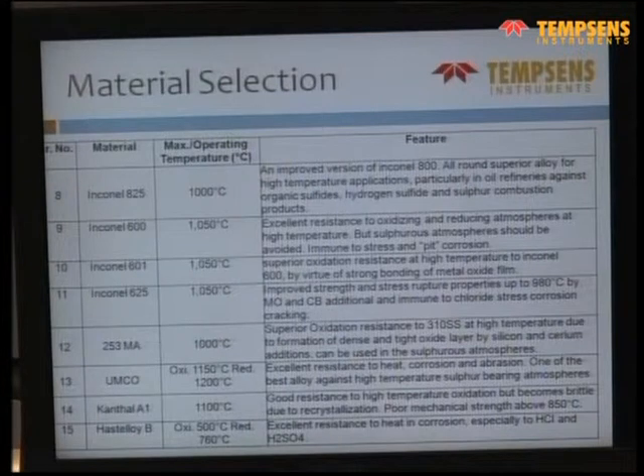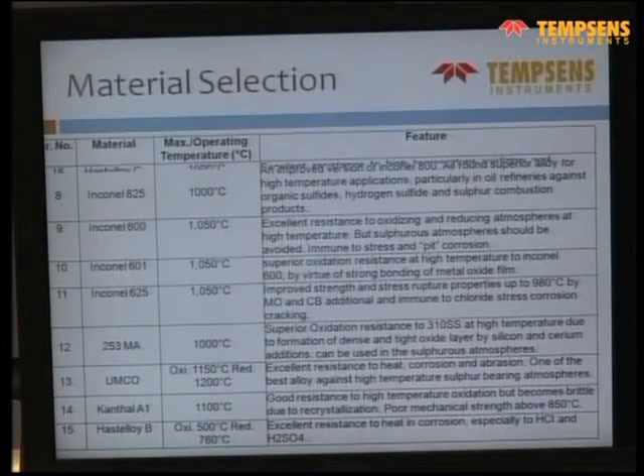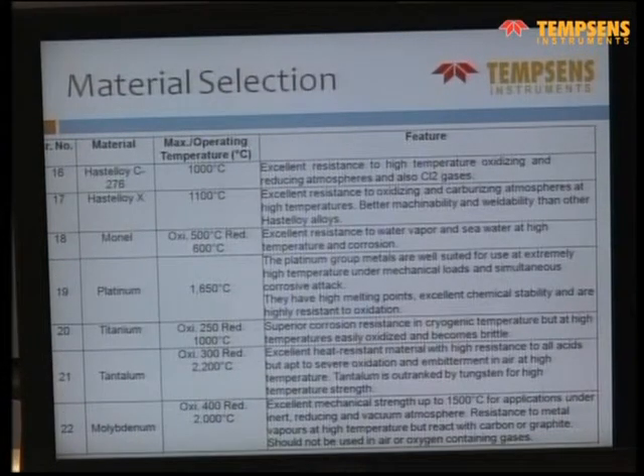Hastelloy is more for acidic applications, for HCl and H2SO4 for chemical. Hastelloy C276 is for high temperature application, Hastelloy X, Monel, also for some chemical applications. Then platinum we are using a lot in glass temperature sensors. In case of molten glass, there is no element which can withstand that kind of aggressive nature, and platinum is a material which is non-wetting for molten glass. So the molten glass is not sticking to platinum. So we are using platinum thermowells for such cases.